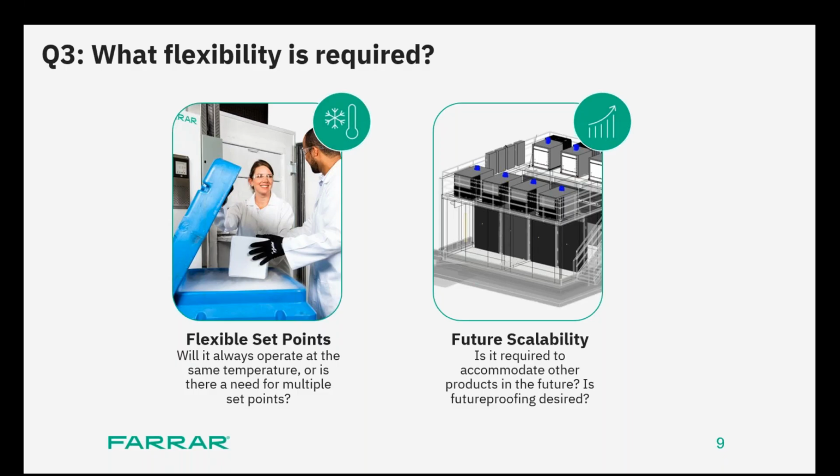And one thing he mentioned to me was that, Rajiv, we store our bulk drug substance products at -70 degrees C and the finished drug products at +5. So we have to have two separate refrigerator versus freezer, right, to accomplish that. Now, wouldn't that be awesome if I had one cabinet or one chamber where initially when I'm storing my bulk substance products, I'm storing them at -70.